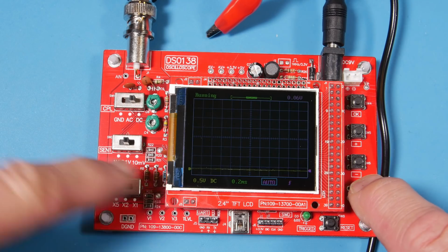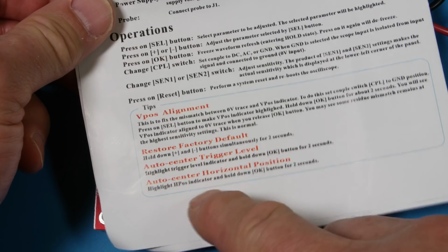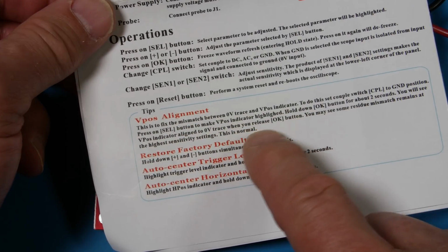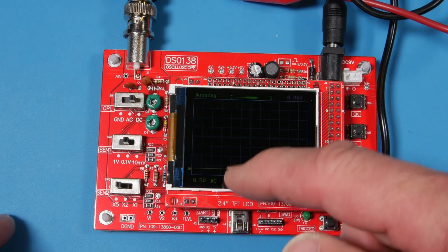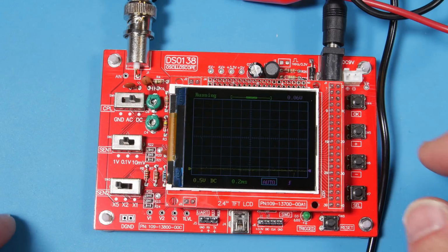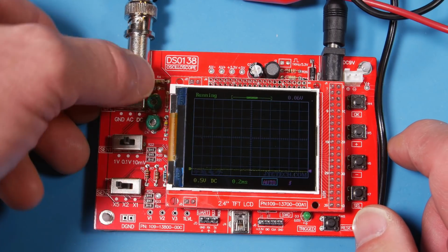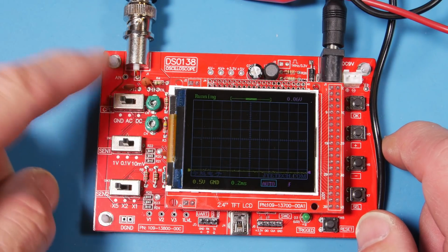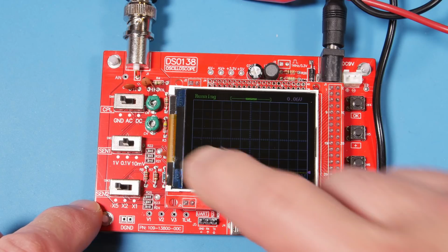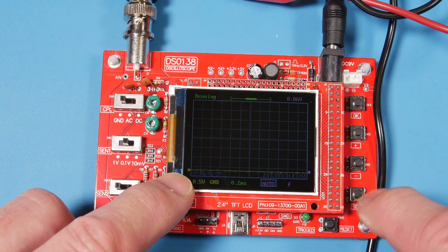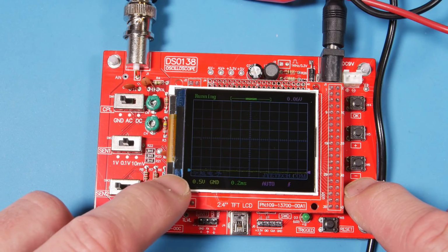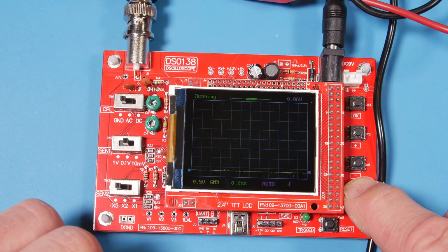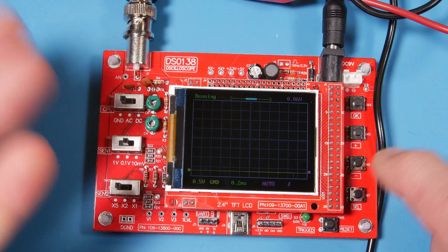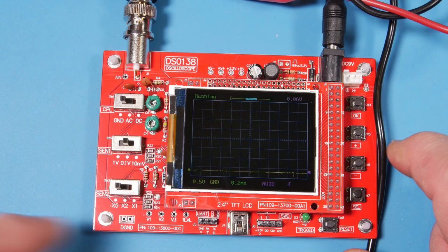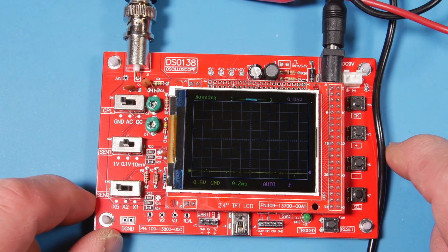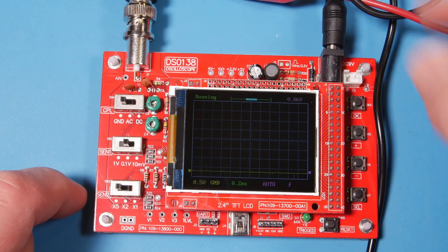Okay, now there's another thing we want to do in this pro tips. I just took a quick read of these. The first one is alignment. What that does is, I guess, the trace can be out of line with the position indicator here. It looks like it's dead on to me, but let's just do it anyway. You put the coupling in ground, and then you select the vertical position. Okay, and then you hold this thing down for 2 seconds, and it kind of highlighted the line. I guess it's done, but it looked like it might have moved just a skosh. So, all right, now I guess we're ready to go back to calibration.